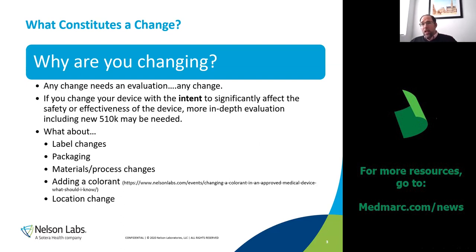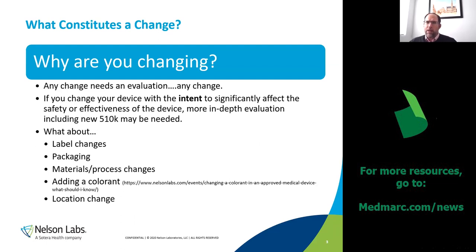Another thing I see a lot of people do is change or add colorants to an already approved device. A while ago this was a very big topic — so much so that the FDA did its own webinar on it. It's cooled down a little bit now because not many people are coloring or changing colorants on patient-contacting portions of devices. But if you are going to change a colorant to a patient-contacting portion, either directly or indirectly, it's definitely something you should know about.